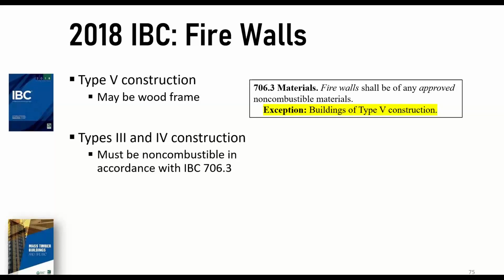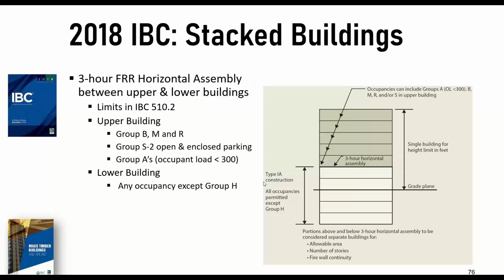wall assembly test, an ASTM E119 assembly test fails by having flame front pass through the wall assembly, or having such increased elevated temperatures within the wall cavity that they exceed the test criteria. I believe it's 250 degrees. If it gets above 250 degrees in the wall assembly, the test stops. You fail the criteria for the testing once those temperature limits are reached, or once the flame penetration goes through the assembly. So there are provisions, again, for those similar to our podium discussions in 510.2.